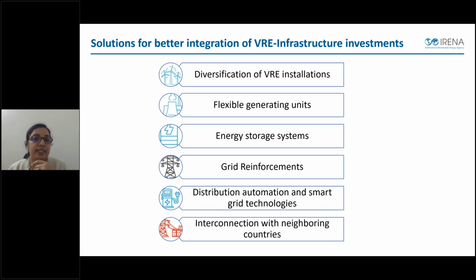In this slide, you can also see some of the solutions which have been recommended under infrastructure investment. There is a grading given to each of these solutions, from low and medium to high, according to their applicability to small island developing power systems. Say, for example, the first one, diversification of VRE installations, is highly applicable in an interconnected power system because of the geographical dispersity of variable resources available. But in case of island power systems, that may not have a high applicability, but low applicability. But in case of flexible thermal generation in small islands, most of the existing generation fleet comprises diesel generation, and it has high ramping capabilities.